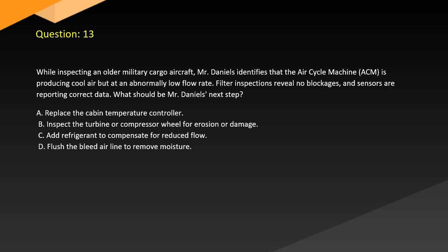Question 13. While inspecting an older military cargo aircraft, Mr. Daniels identifies that the air cycle machine, ACM, is producing cool air but at an abnormally low flow rate. Filter inspections reveal no blockages and sensors are reporting correct data. What should be Mr. Daniels' next step? A. Replace the cabin temperature controller. B. Inspect the turbine or compressor wheel for erosion or damage. C. Add refrigerant to compensate for reduced flow. D. Flush the bleed air line to remove moisture.